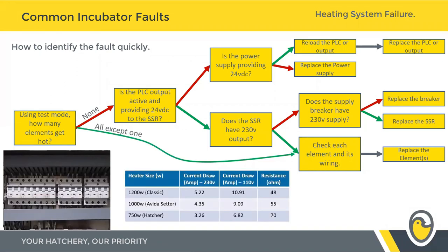Back to the test mode: if all except one heating element heats up, you can rule out a large portion of the decision tree because you know the controls are working, the solid state is working, and you can go straight to diagnosing the individual heating element. The table at the bottom of this page shows the expected current draw and resistance for each of our heating elements — these will vary slightly based on your local voltage, but it's worth documenting these specifically for your site.